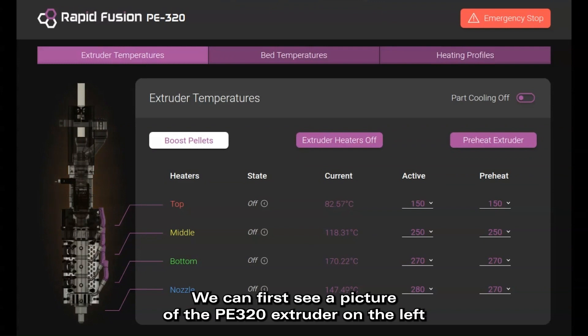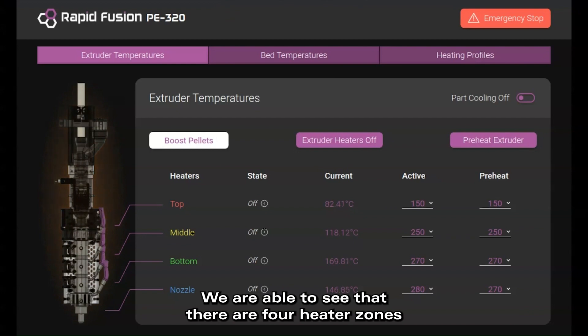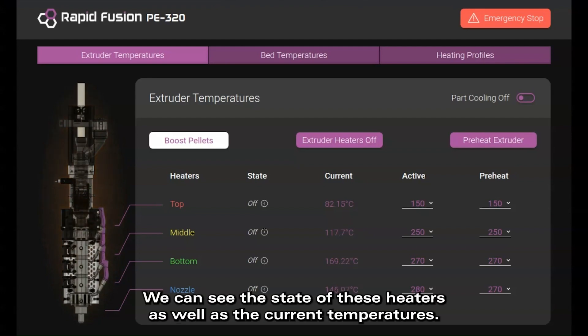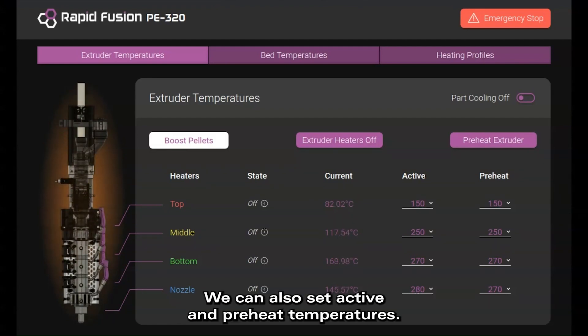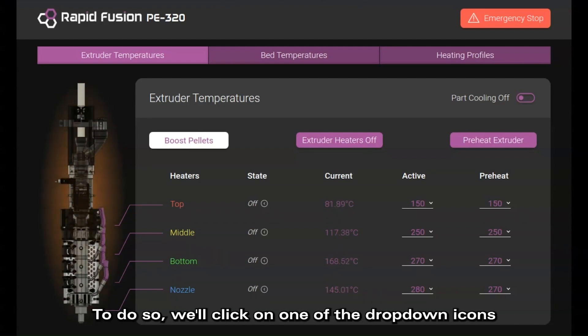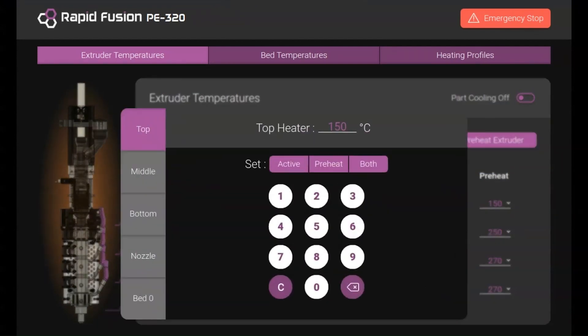Let's move on to the core features of the Extruder Temperatures page. We can first see a picture of the PE320 Extruder on the left. Moving to the right, we are able to see that there are four heater zones: top, middle, bottom, and nozzle. We can see the state of these heaters as well as the current temperatures. We can also set active and preheat temperatures by clicking on one of the drop-down icons on the active column, which brings up a temperature pop-up with a number pad to enter the desired temperatures.